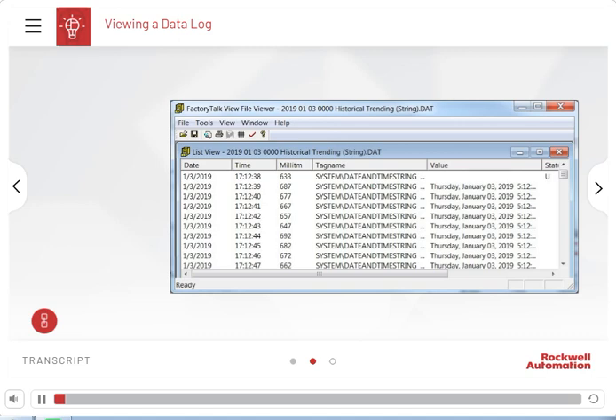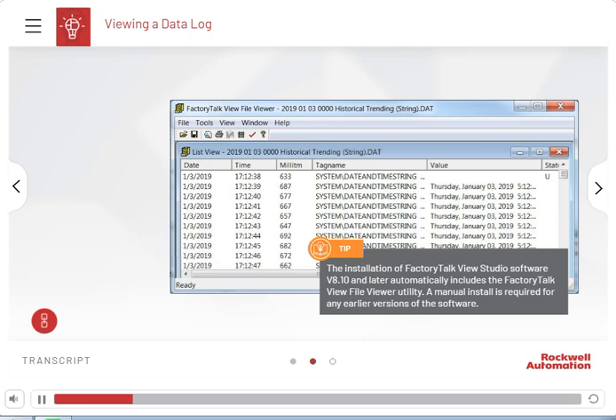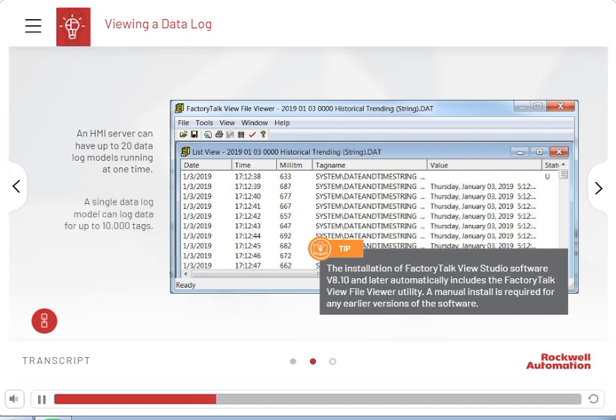Once you have created and started a data log, you can then view the logged data in a trend or in the FactoryTalk View File Viewer. Here is an example of a file set data log model viewed in the FactoryTalk View File Viewer utility. Installation of FactoryTalk View Studio software version 8.10 and later automatically includes the File Viewer utility; a manual install is required for earlier versions. An HMI server can have up to 20 data log models running at one time, and a single data log model can log data for up to 10,000 tags.